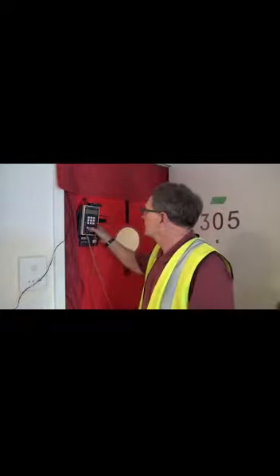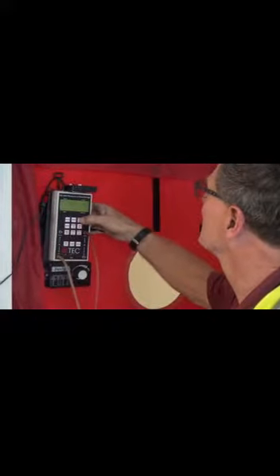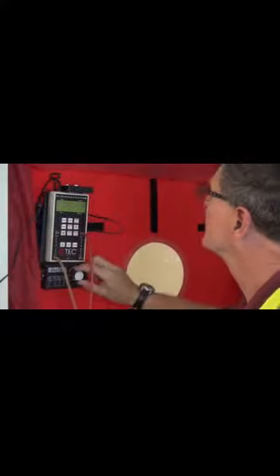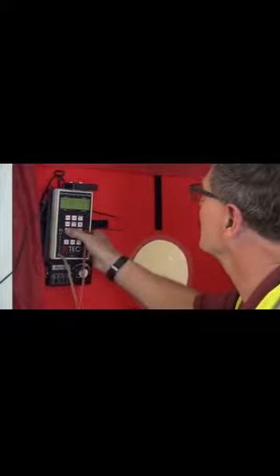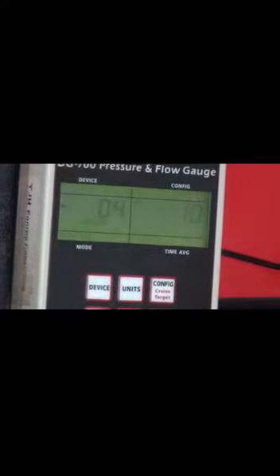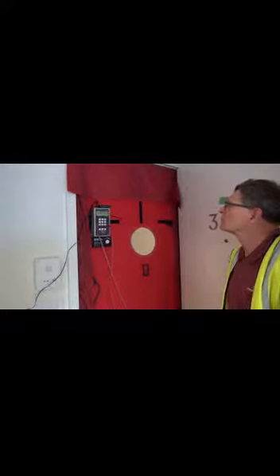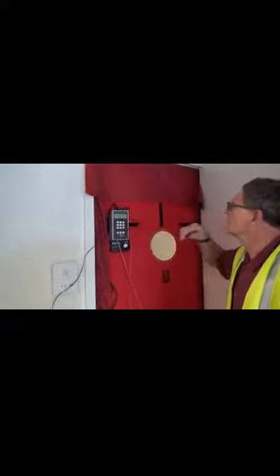We're at Unit 305 — this is Sage on Prospect, LEED for Homes multifamily apartment. This is the final test day; we're setting our blower door up and doing a pressure flow test at 50 pascals for air leakage. This unit is 932 square feet. Our target leakage — we have to be under 640 CFM for this unit to pass five air changes per hour for LEED. We're getting close to our 50 pascals at a 5-second average.